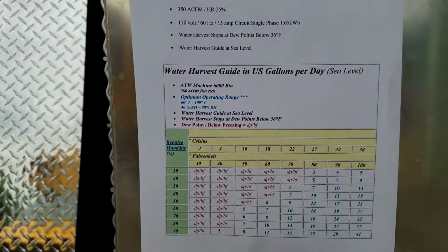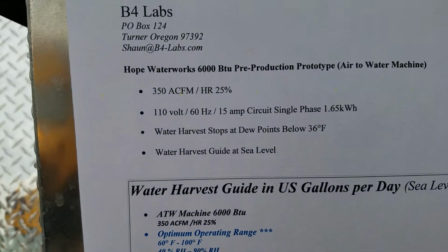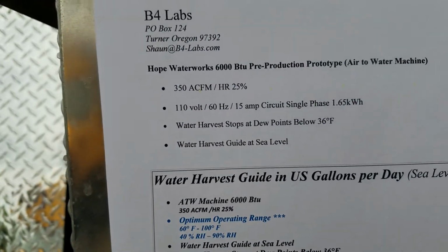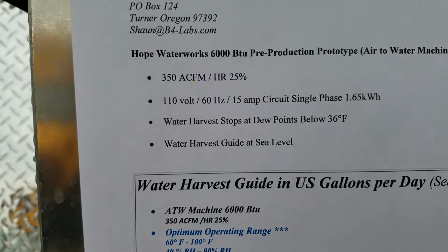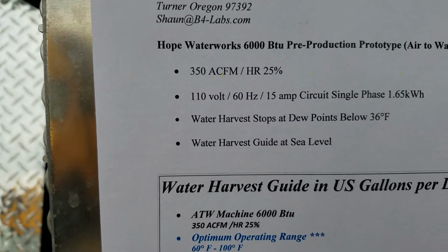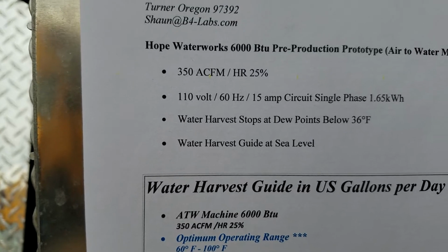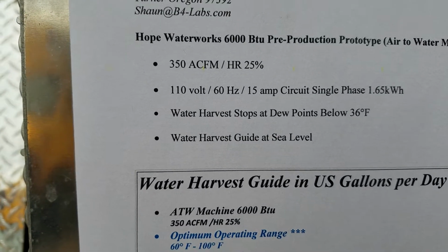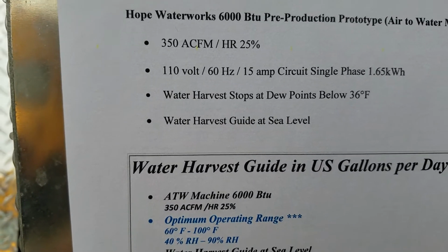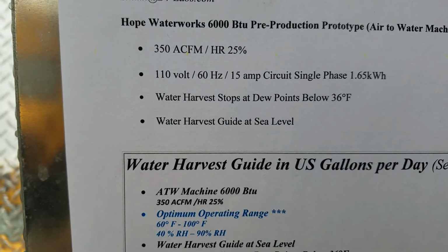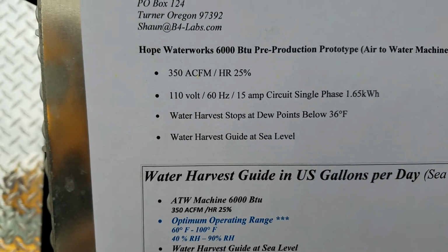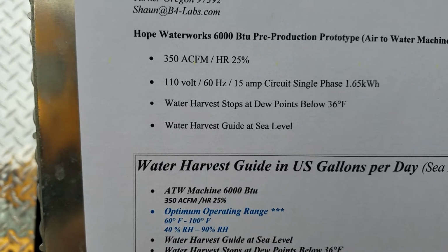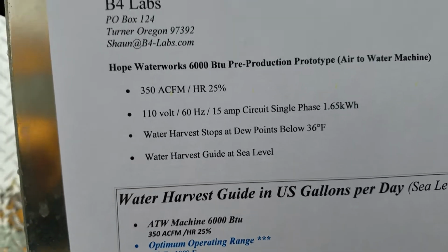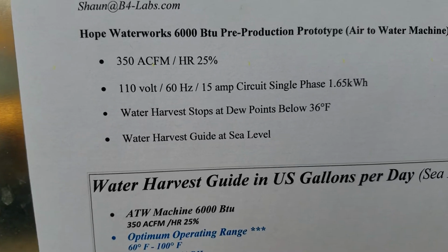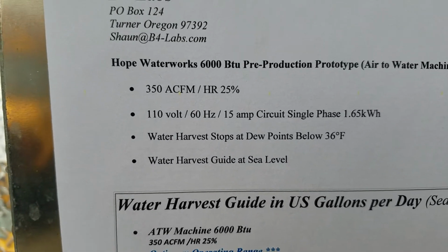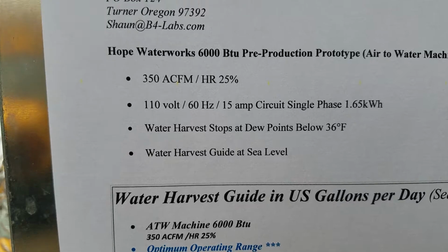So this is the first chart that we're going to look at. There's a definition of the machine up above describing it's processing 350 actual cubic feet per minute through the machine. The harvest rate of this machine is 25%. In other words, of the airstream that's moving through the machine, we're removing 25% of the moisture that's in the air. As we go up in size in BTUs, we're able to extract 40%. That's another reason why the larger BTU sizes are more efficient.